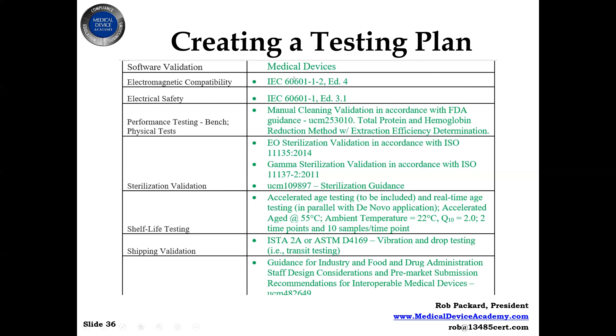Here's the template that we use — just part of it, it actually has some stuff above and below. We have software validation, a bunch of guidance documents, and IEC 62304 is the standard for software validation. Here's the standard for EMC testing, here's the standard for electrical safety — there's a different one for IVD products — and then we have manual cleaning validation, which might be applicable to your product if it's reusable. We have sterilization guidance documents that might be applicable, shelf life testing, and shipping validation and transit testing.